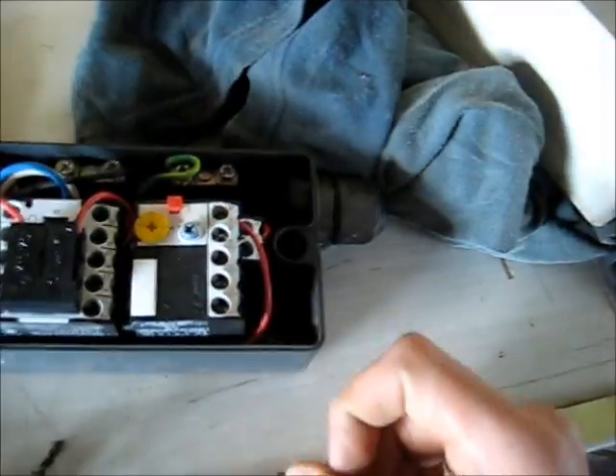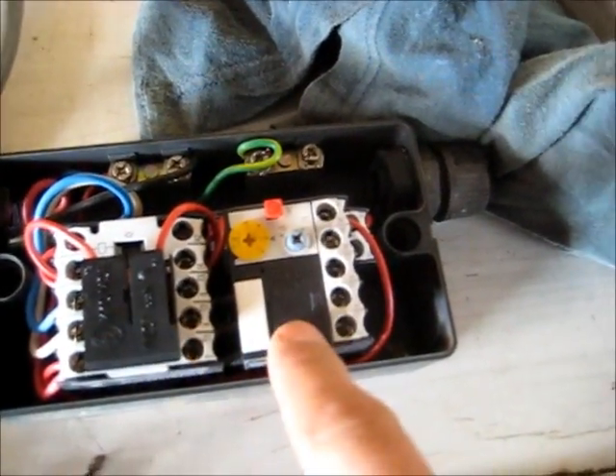I'll open it up and show you what it looks like inside. It's made by Moeller in Germany. This is obviously a three phase switch setup. It starts here, then it drives the contactor when you press that button - so that goes there, presses against there, and it drives that contactor. The stop button has a tab which hits that and pops it all together. So we've got live one, live two, and live three. There are little jumpers here joining from this contactor to this relay - yeah, contactor - and that's it.